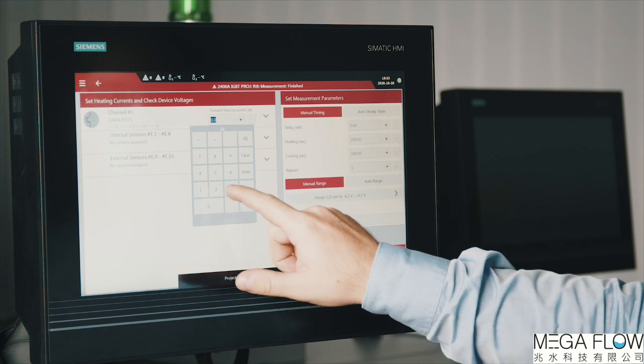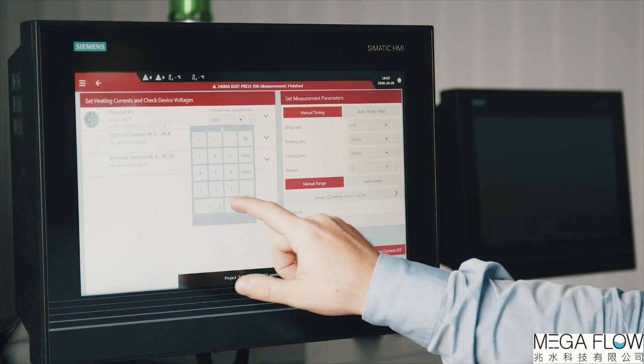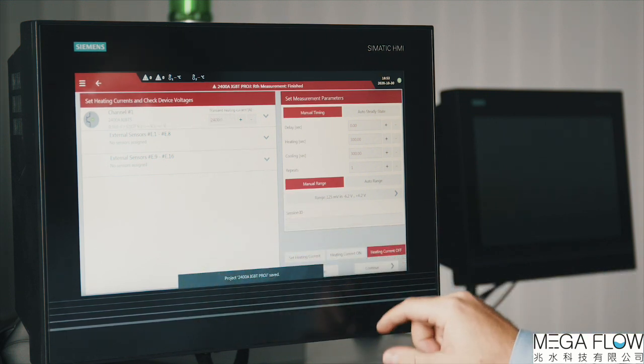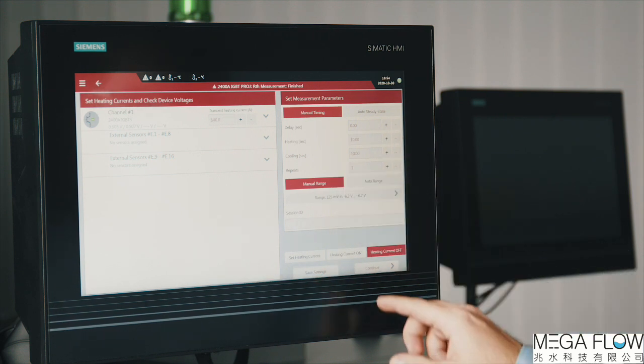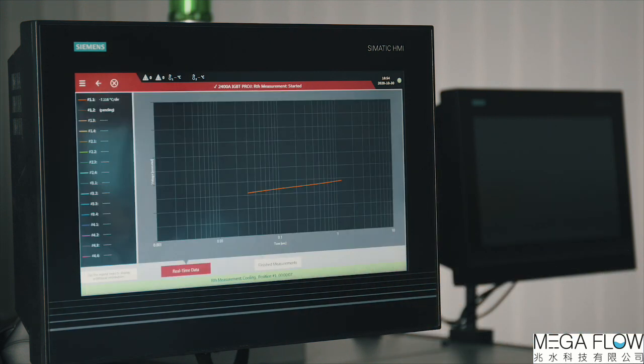The desired heating current level and the measurement timing parameters need to be filled. You can freely configure heating and cooling time. By clicking Continue, the measurement will start. First, the system heats up the device. Then, after the set heating time, the heating is turned off and the thermal transient is measured.